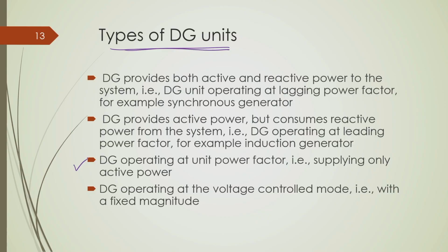Therefore we can categorize DG units into three categories. One category behaves similar to a synchronous generator, delivering both active and reactive power. Some DG units operate only at unity power factor, supplying only active power, not reactive power. And some DG units supply active power but consume reactive power, particularly induction generator type systems.